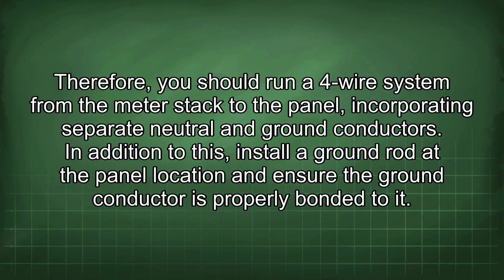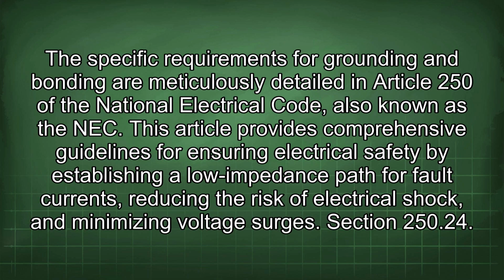In addition to this, install a ground rod at the panel location and ensure the ground conductor is properly bonded to it. The specific requirements for grounding and bonding are meticulously detailed in Article 250 of the National Electrical Code, also known as the NEC. This article provides comprehensive guidelines for ensuring electrical safety by establishing a low impedance path for fault currents, reducing the risk of electrical shock, and minimizing voltage surges.